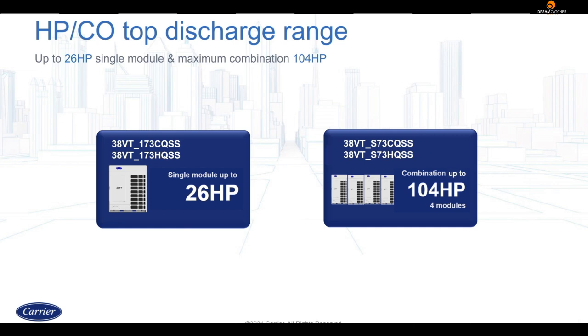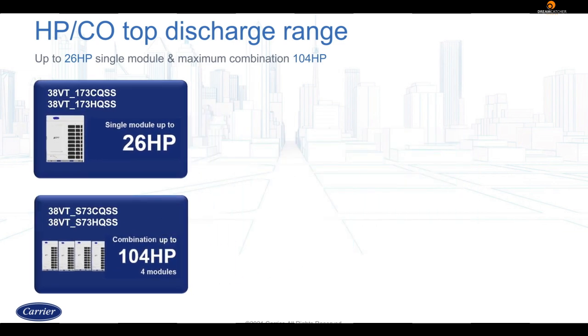7 stands for Series 7 and 3 stands for the power supply. If the unit is cooling only, then C follows, or if it's a heat pump, then H is used. The next letter denotes the supply origin, in this case Q, which means China. The next 2 letters depict the region it's made for, and SS stands for South Asia. Single modules offer a capacity of up to 26 HP, and combinations can have capacity up to 104 HP with the help of 4 modules.